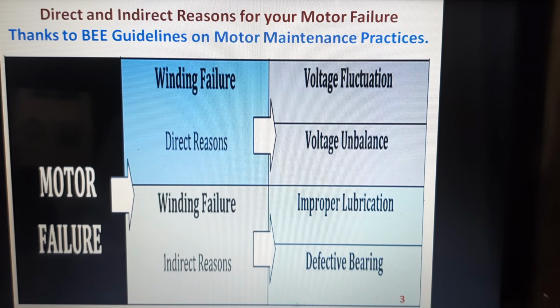Thanks to the Bureau of Energy Efficiency guidelines on motor maintenance practices, the direct and indirect reasons for your motor failure are listed. You can see the direct reasons for winding failure. It can happen due to voltage fluctuation at the incoming or the voltage unbalance at the terminals of your motor. And winding failure due to indirect reasons is the improper lubrication given to the motor, the defective bearing, or the blocked ventilation in the motor.